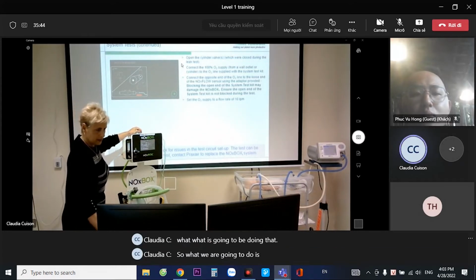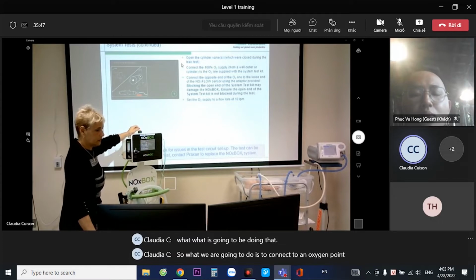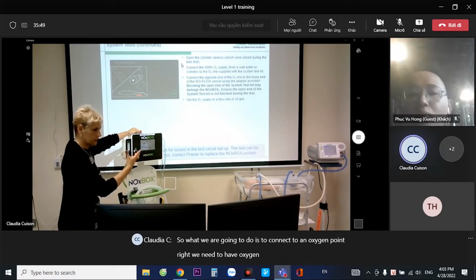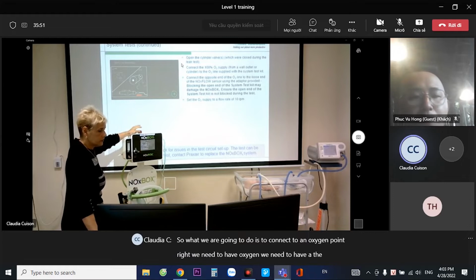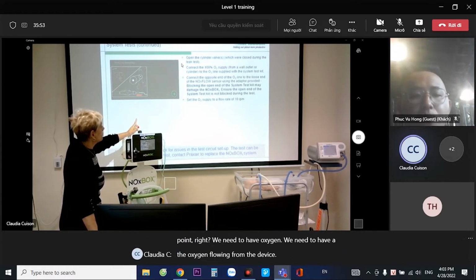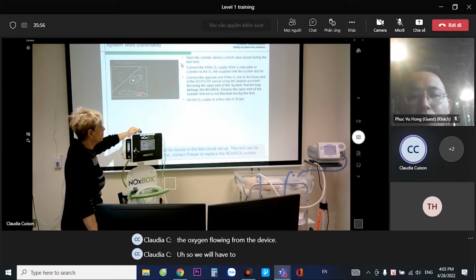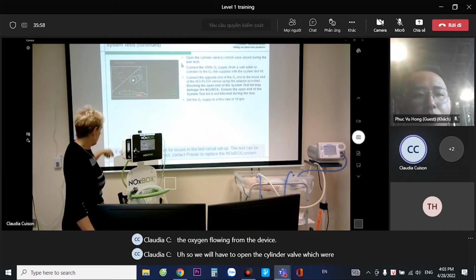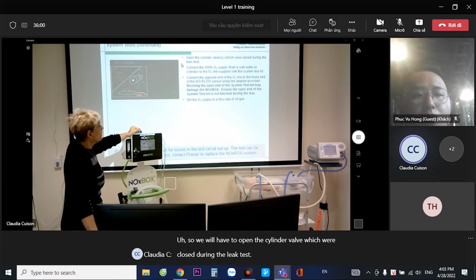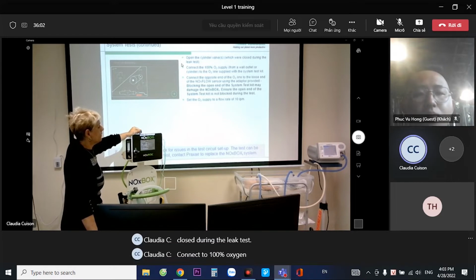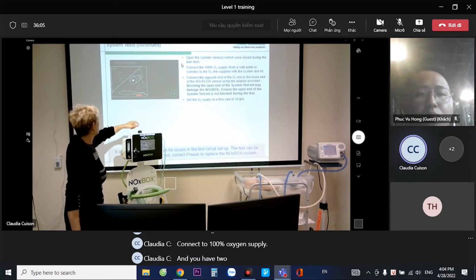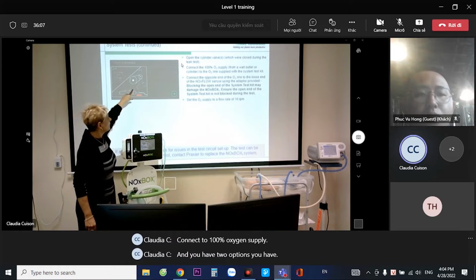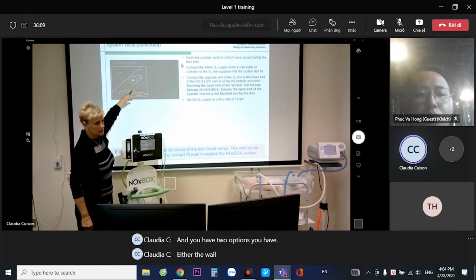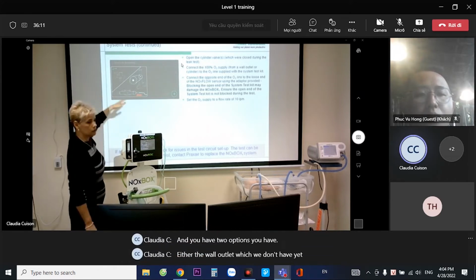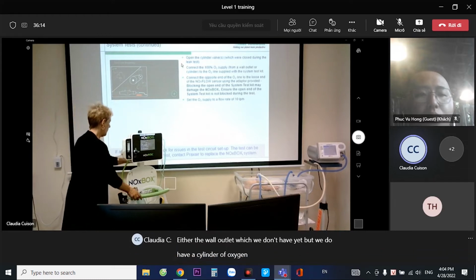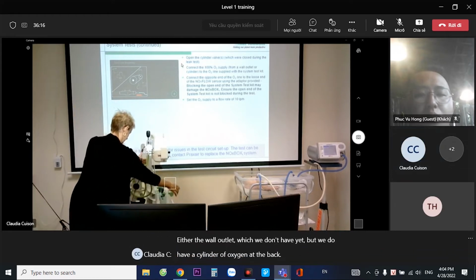So what we are going to do is to connect to an oxygen point, right? We need to have oxygen. We need to have the oxygen flowing from the device. So we will have to open the cylinder valve, which was closed during the leak test, connect to 100% oxygen supply, and you have two options. You have either the wall outlet, which we don't have here, but we do have a cylinder of oxygen at the back.